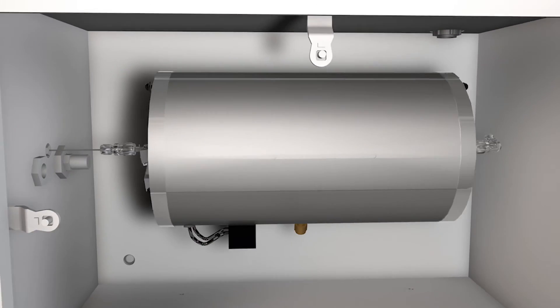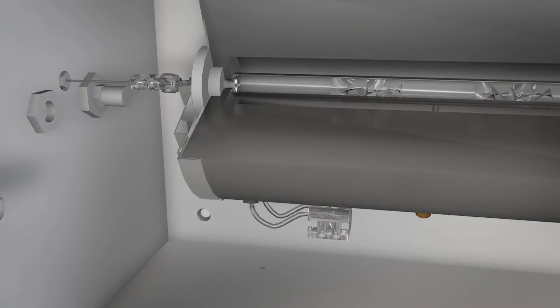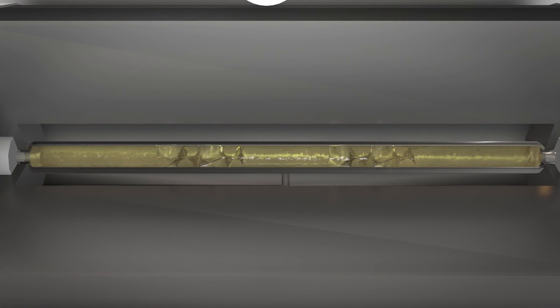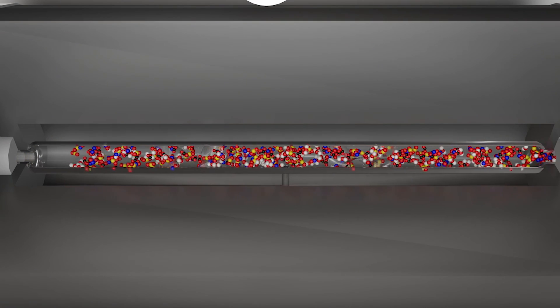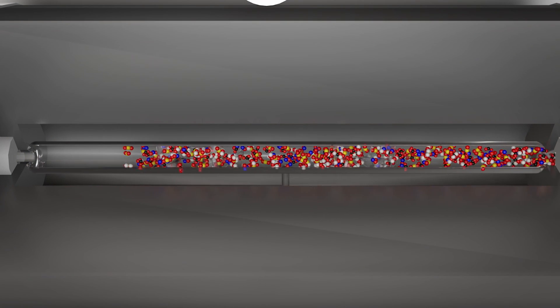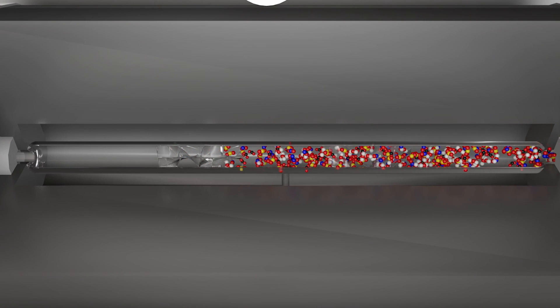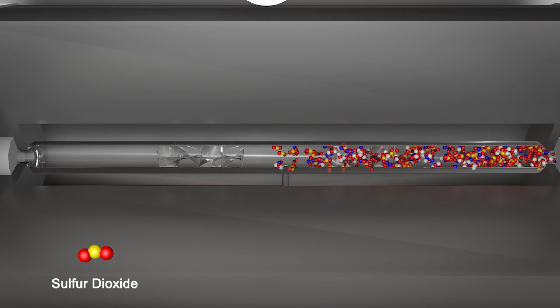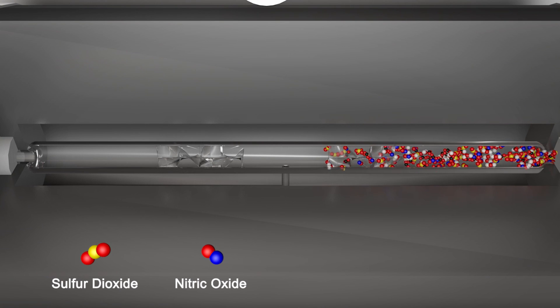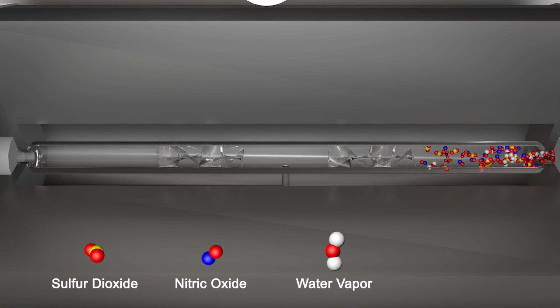As the sample is moved into the furnace, it is mixed with combustion gas and injected into Antec's unique furnace. Once in the furnace, the sample is completely combusted at 1,050 degrees Celsius. This converts all sulfur species to sulfur dioxide and nitrogen to nitric oxide. The hydrocarbons are converted to water vapor and carbon dioxide.